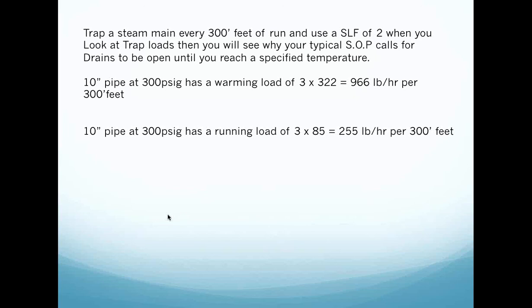Now, that's on a warming condition, warming load. In a running condition, we're going to have that 10-inch pipe, 300 psig, has a running load of 3 times 85 pounds per hour per 100 feet. And remember, the 3 is because we put a trap every 300 feet, so that's the 3 times the 85 gives us a load of 255 pounds per hour per 300 feet.